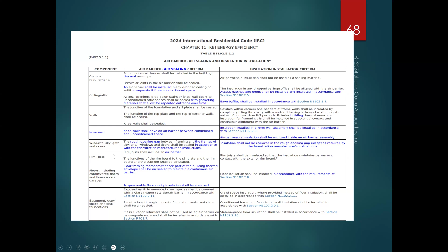whether you caulk it or whether you chink it with foam or anything like that. So, continuation of this table, we're looking at spaces. So showers, tubs, and fireplaces adjacent to the building thermal envelope. Got to have an air barrier separating the insulation of the building thermal envelope from the shower, tub, or fireplace assemblies. So we're seeing a lot of times that you've got a fireplace on the outside wall. The void just gets left open and there is no air barrier in there. And so that creates leakage around the fireplace into that void and outside.